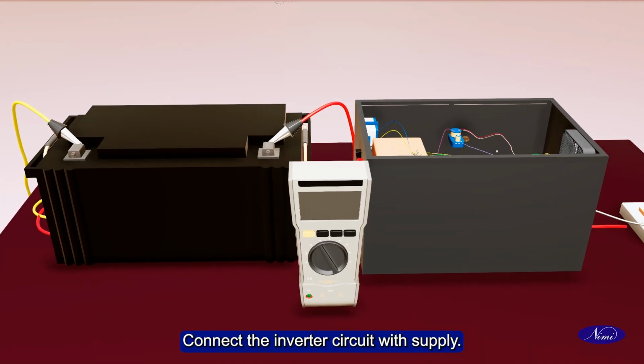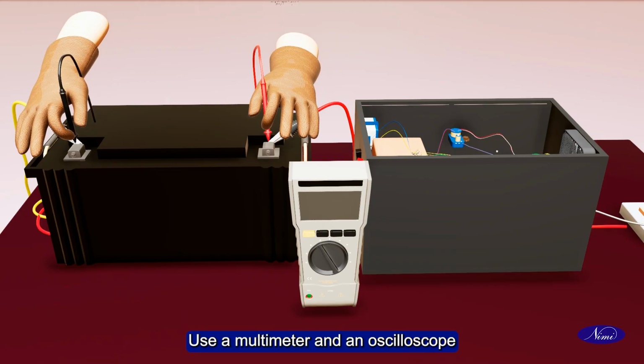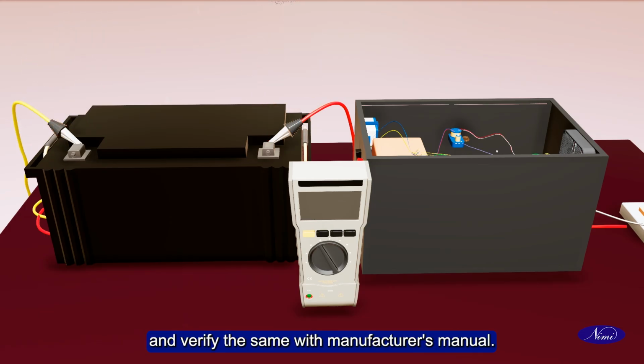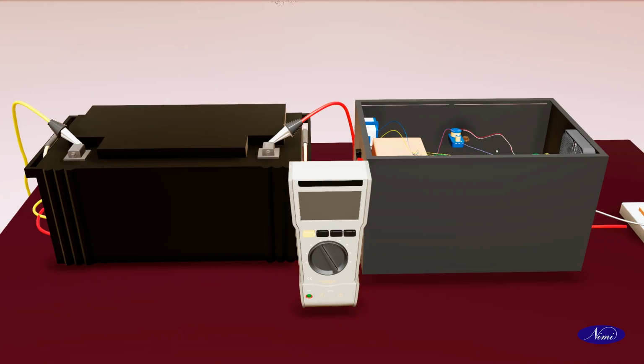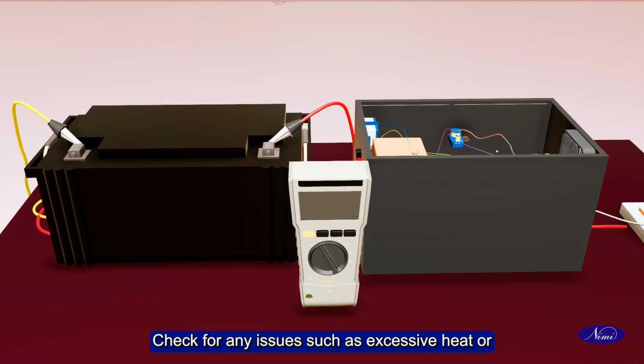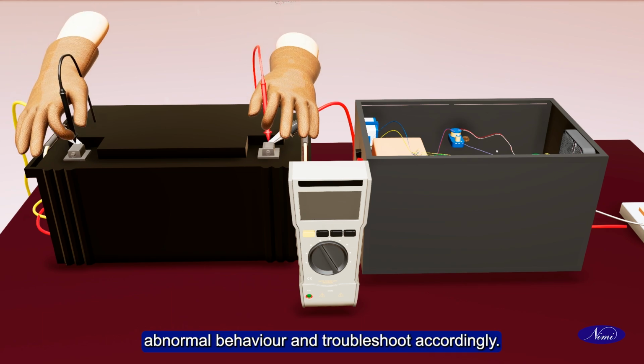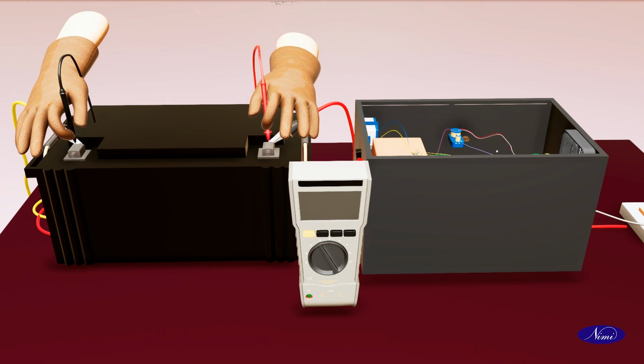Connect the inverter circuit with supply. Disconnect the main AC supply and test the output of inverter by connecting load and note down the performance. Use a multimeter and an oscilloscope to measure voltages, currents and waveforms. Check the backup time of the inverter and verify the same with manufacturer's manual. Check for any issues such as excessive heat or abnormal behavior and troubleshoot accordingly.